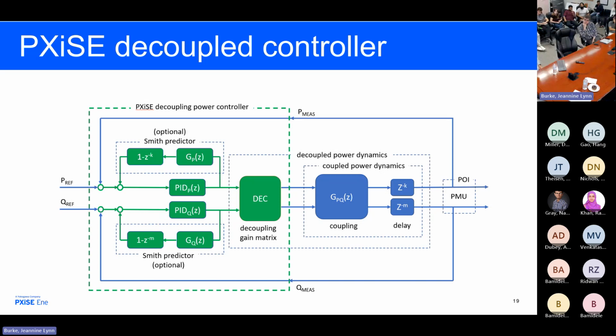The key here, one of the keys in this controller, is this derivative term is not off of the error. Every PID controller in the world today calculates the derivative off of the error signal. That's wrong, because if you do a set point change, the error signal is going to have an impulse function, almost, and that's going to cause the derivative action to go nuts. So you don't want that. You want the derivative action on the measured value. So we call it the PIFD, proportional integral filtered derivative. So this is implemented in the control system.